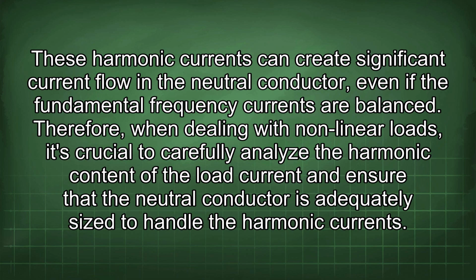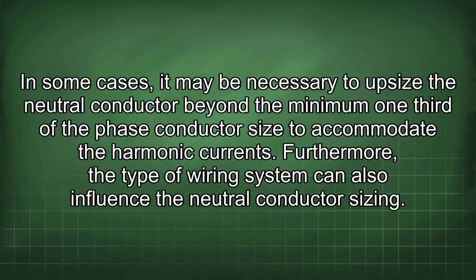Therefore, when dealing with nonlinear loads, it's crucial to carefully analyze the harmonic content of the load current and ensure that the neutral conductor is adequately sized to handle the harmonic currents. In some cases, it may be necessary to upsize the neutral conductor beyond the minimum 1/3 of the phase conductor size to accommodate the harmonic currents.